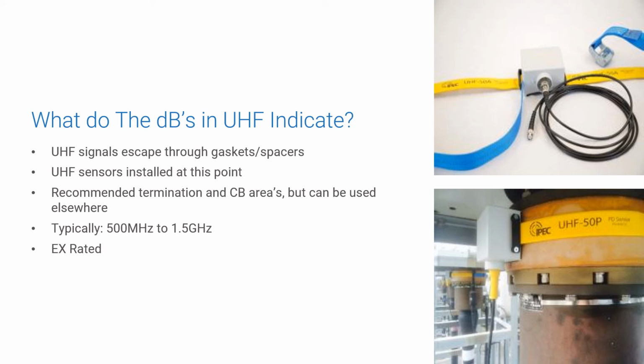UHF signals escape through gaskets and spacers. The UHF sensor should be installed at this point. Recommended termination in CB areas, but it can also be used elsewhere. Typically, the partial discharges will be in a range of 500 MHz to 1.5 GHz. This device is intrinsically rated or EX rated.